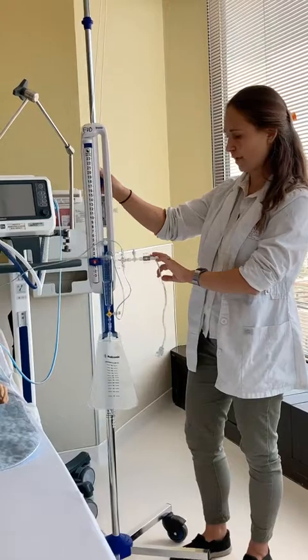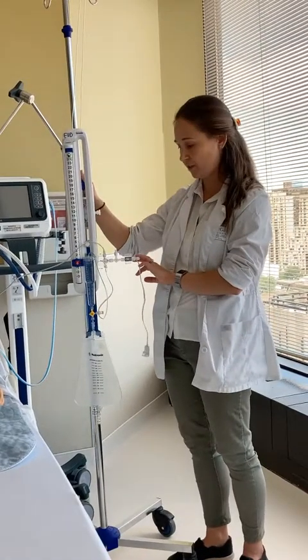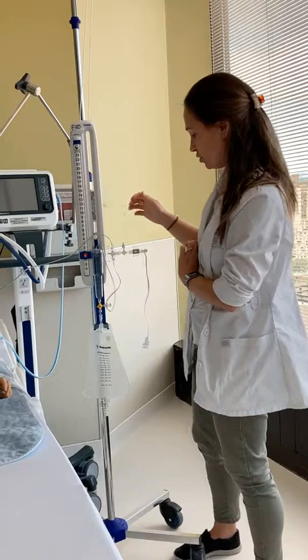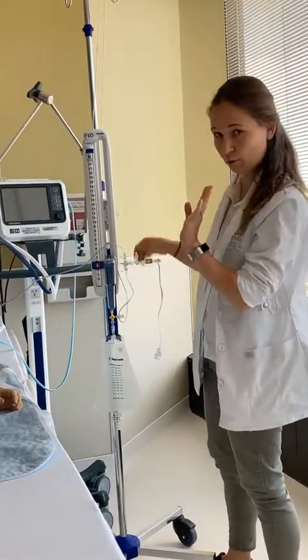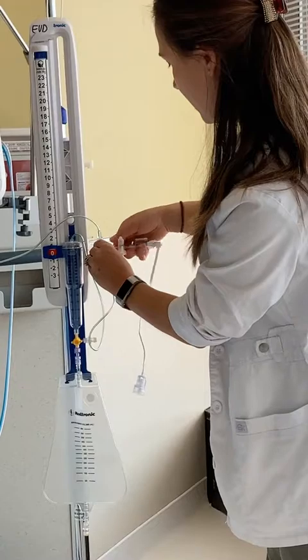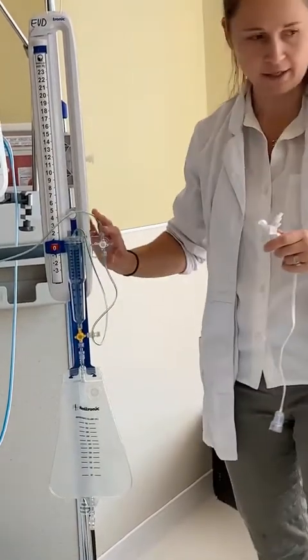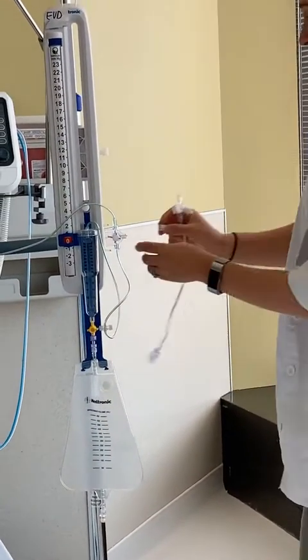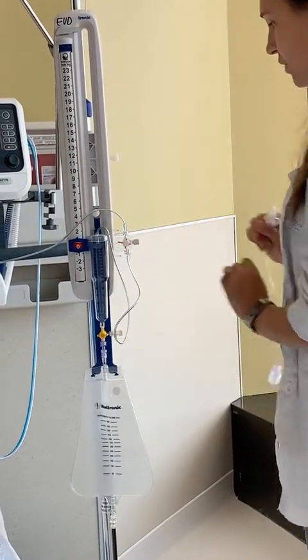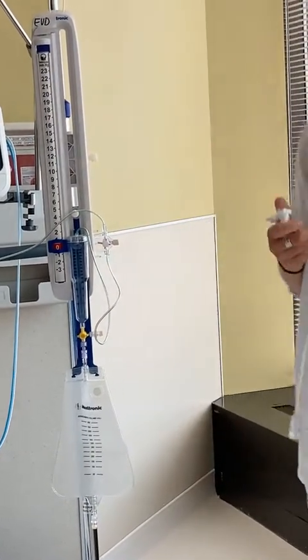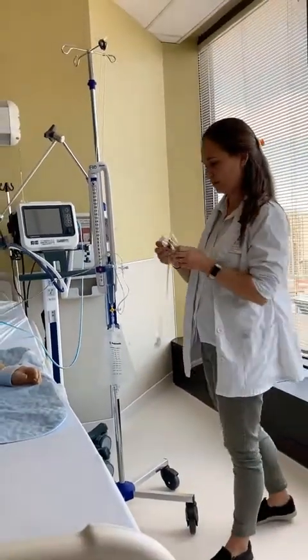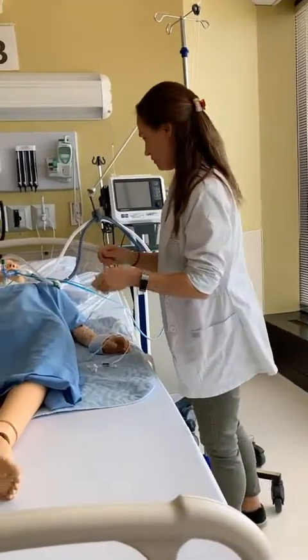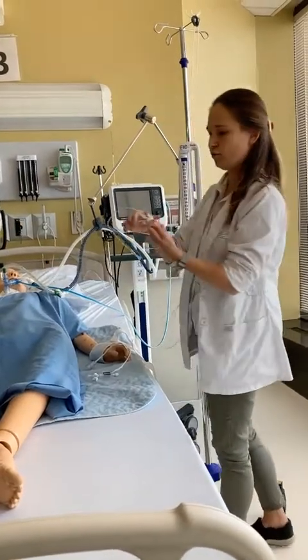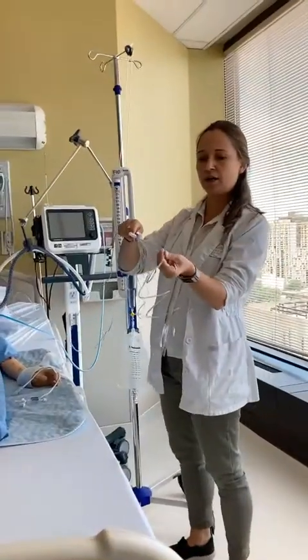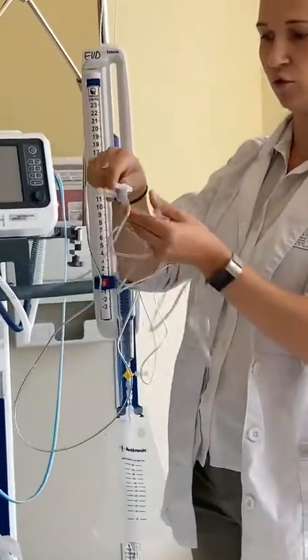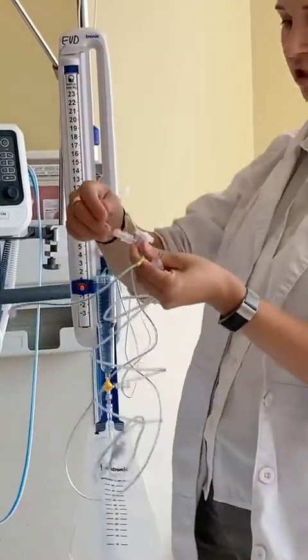Now, this is just one way to configure your system for ICP monitoring. Another way to do this is, again, I would be sterile when I'm setting up my system. I would not connect my transducer here, but instead I would just keep my sterile, not vented cap here. I will take extra pressure tubing that comes in a sterile package, and I can connect the pressure tubing directly to where my ventricular drain sits. So this is where my CSF measurement line originates.